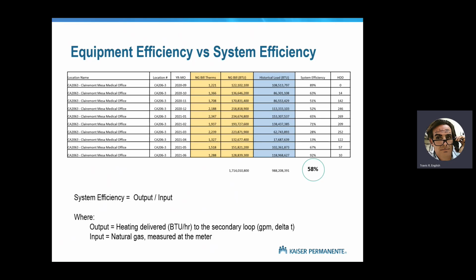That means you can sum up the load for every hour in the system in a month, and then compare that to the natural gas bill that you paid for that month. And that gives you the system efficiency. In this case, looking at a couple of months, the system efficiency was 58%. I want to make sure everyone understands this. System efficiency is very different from equipment efficiency.